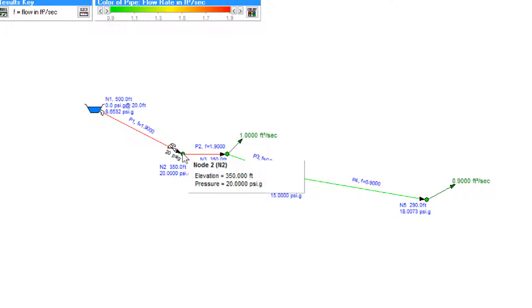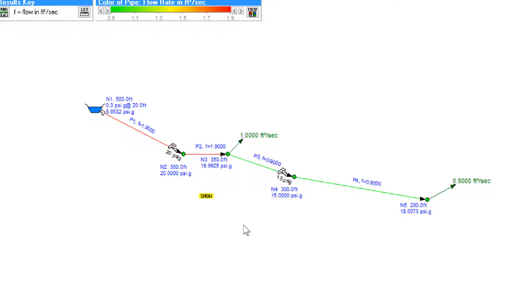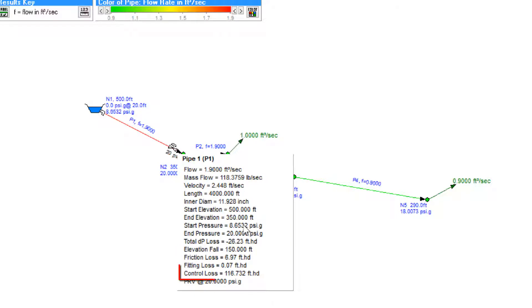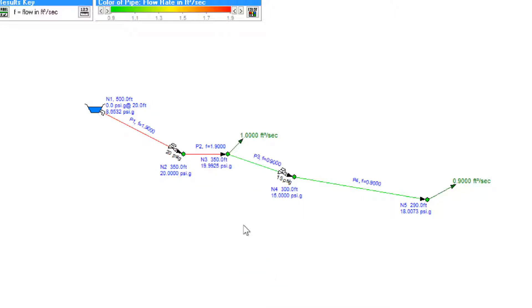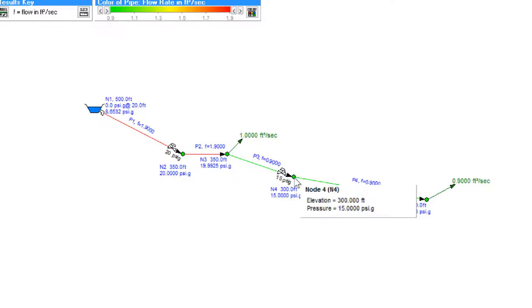That's what the pressure reducing valve was set to reduce to. If we hover the mouse over the pressure reducing valve, we can see in the results list a control loss figure of 116.7 feet of head — the amount of loss the pressure reducing valve has introduced into the system to achieve the required pressure at the following node. Node 4 has a pressure of 15 psi gauge because the pressure reducing valve on pipe 3 is reducing the pressure to 15 psi gauge.